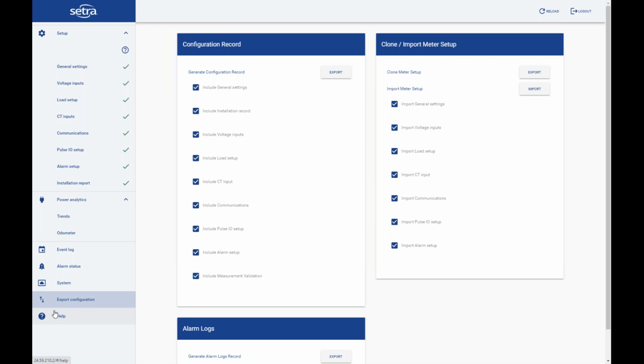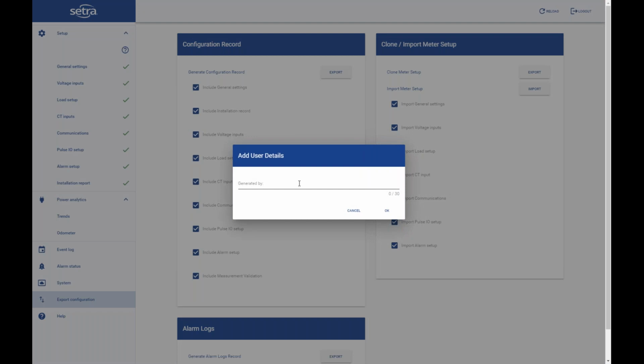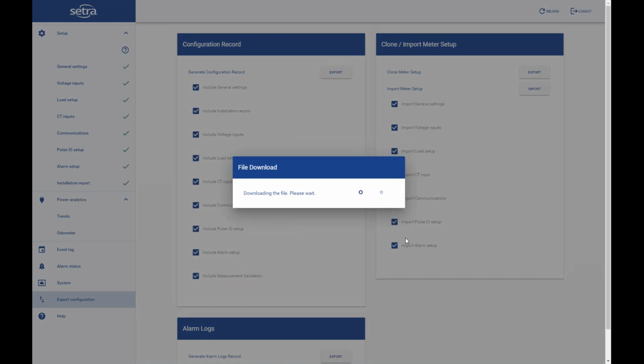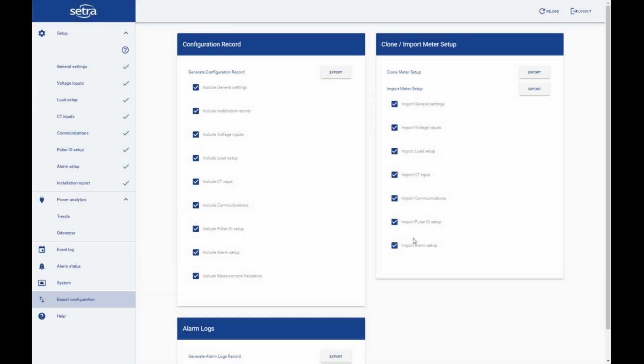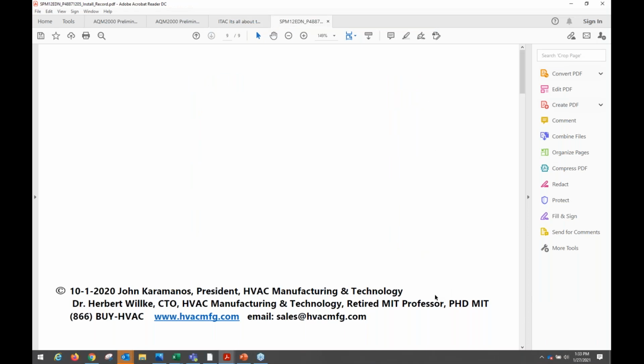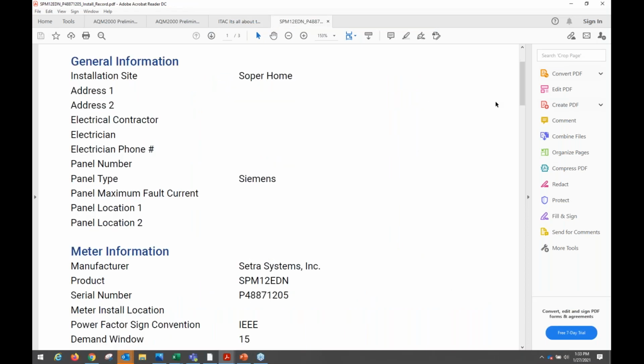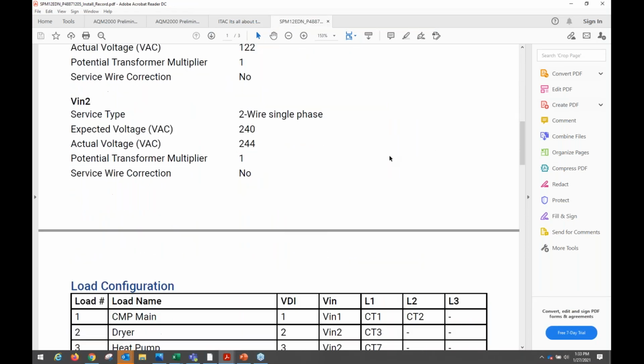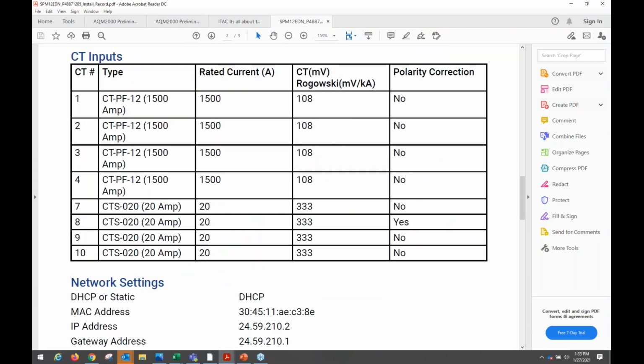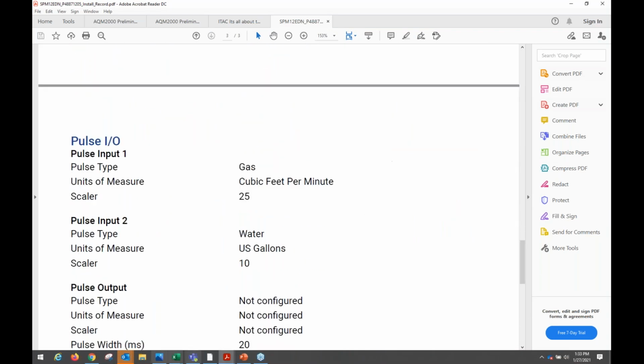On the export configuration, this is where you can export that installation report. So you can type in the user who's generating that report, and the meter will generate a PDF of that installation report, as you can see here, that has all the configuration data and anything that's set up within that meter.